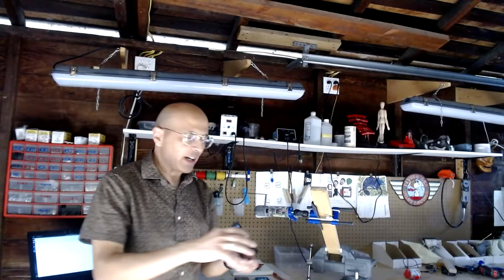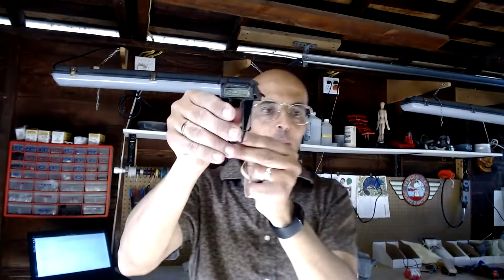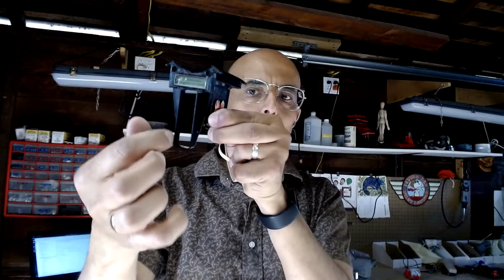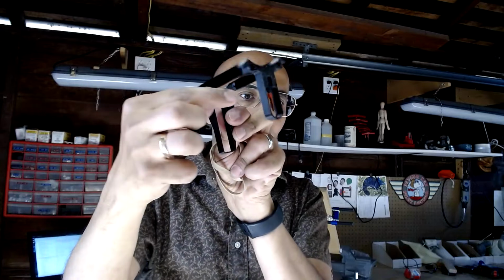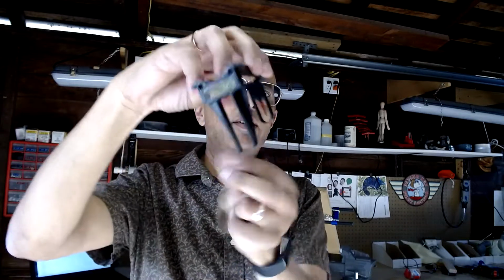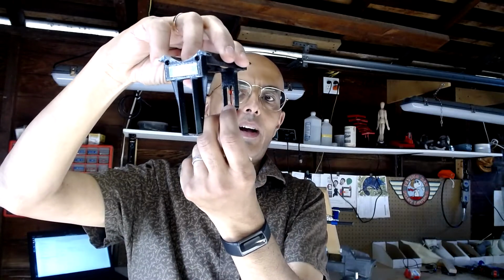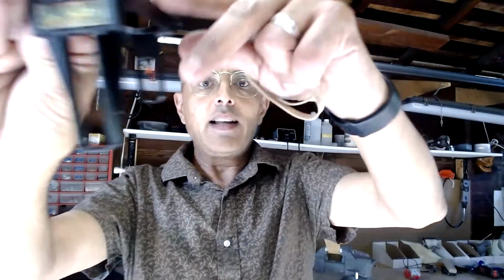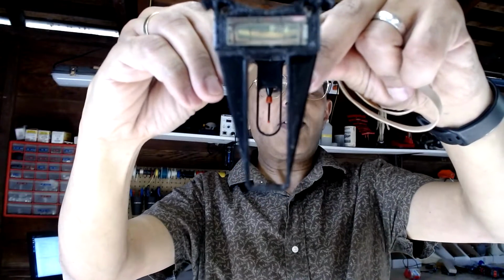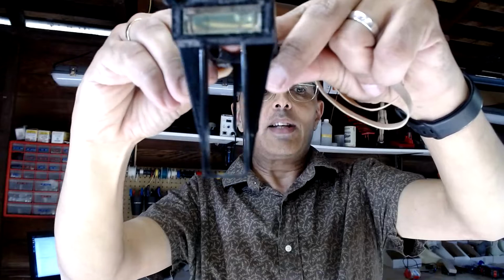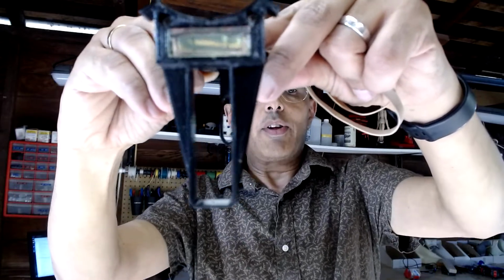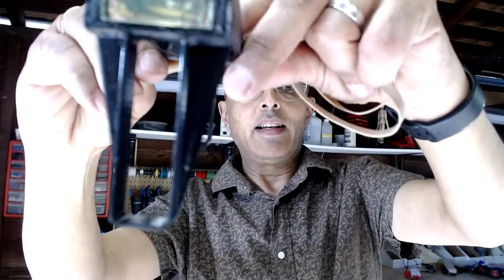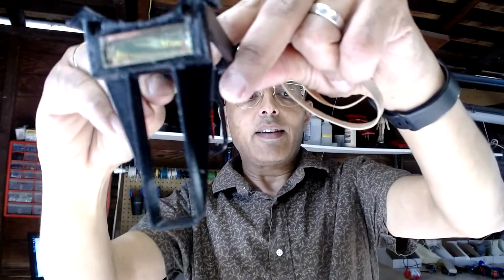Now, we provide a bore sighting attachment with the probe, and you notice it has a spirit level over here and what looks like sort of a vertical peep sight, and over here it has a corresponding vertical oval, and there's a little red dot or colored dot with a fiber optic illumination. So if you look through that, you can see that you can line up the vertical parts together and then use that dot for sighting, and you can move up or down as necessary to get that dot wherever you want. So here you go, you should see it pretty lined up, and then you can move up or down and keep the dot centered and line up this basically as a bow hunting sight or a bow sight. And then you can use the spirit level to level this, to level your probe.